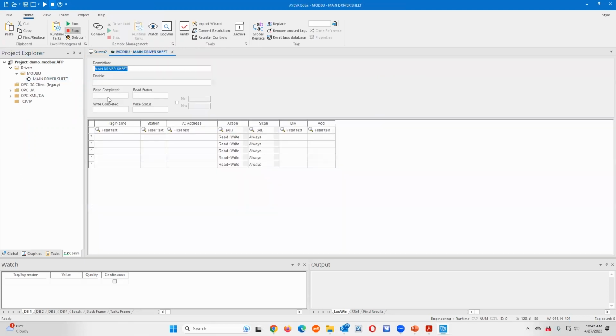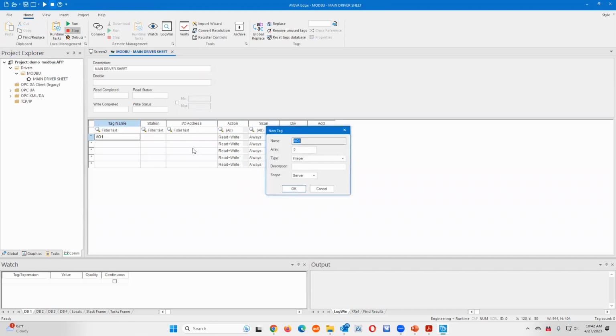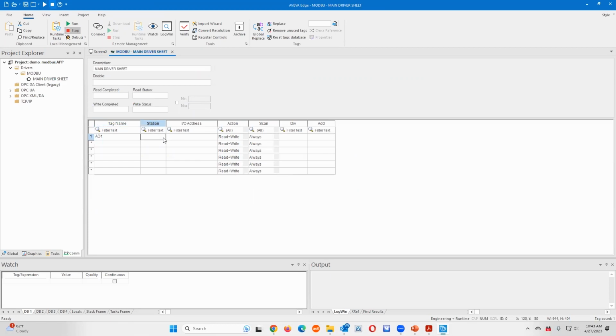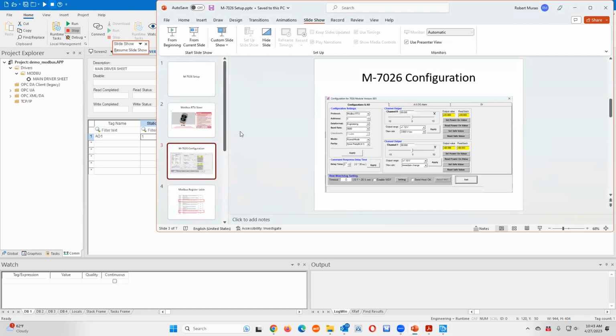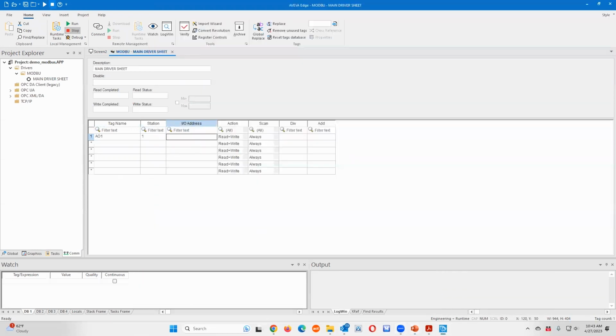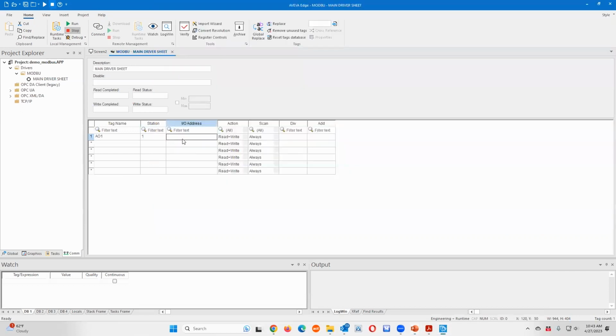And then you click on the Modbus driver sheet, you create a tag name, I'll call it analog output 1, and station ID is the Modbus address. Okay, which in this case was 1. That's based on my page right here where it says address 1 right here. And then the tag value based on the Modbus register table, which is shown here, is 4x33. So we do 4x:33. So it'd be like that. And this is a read write tag.